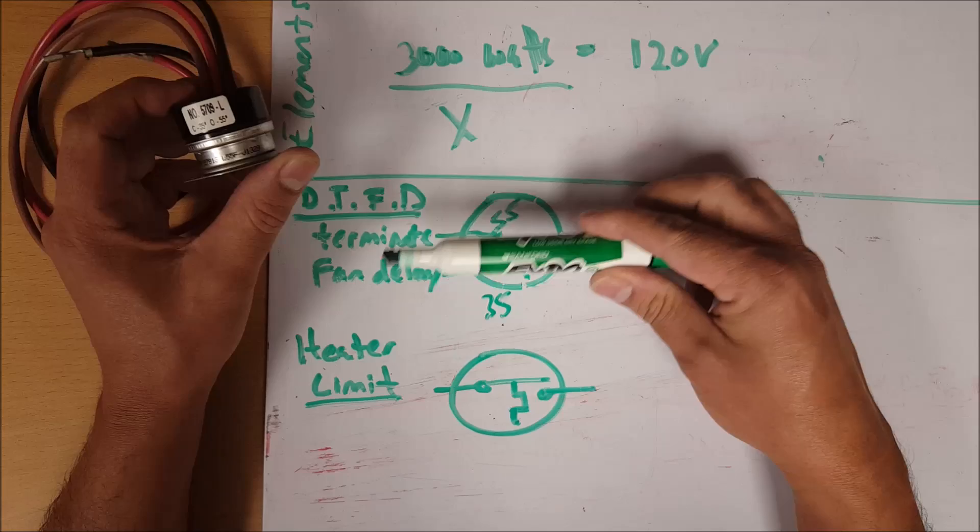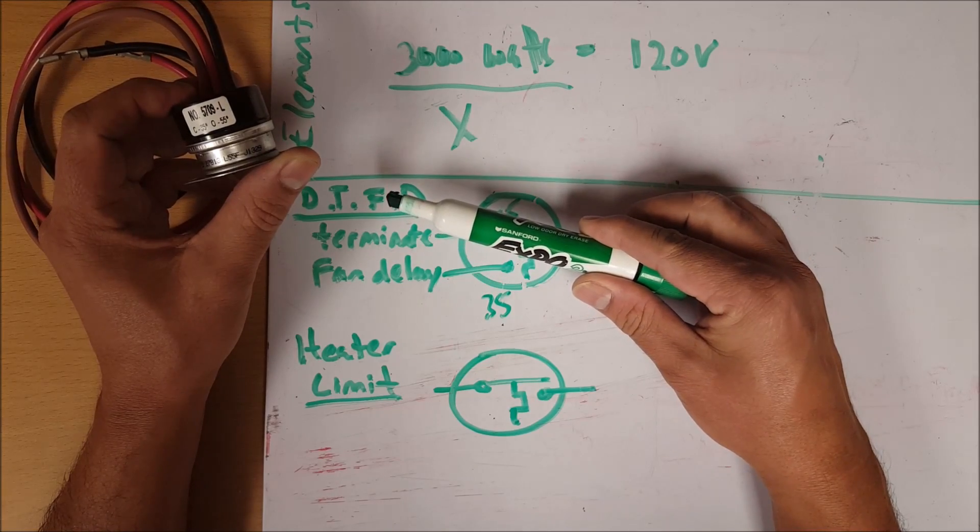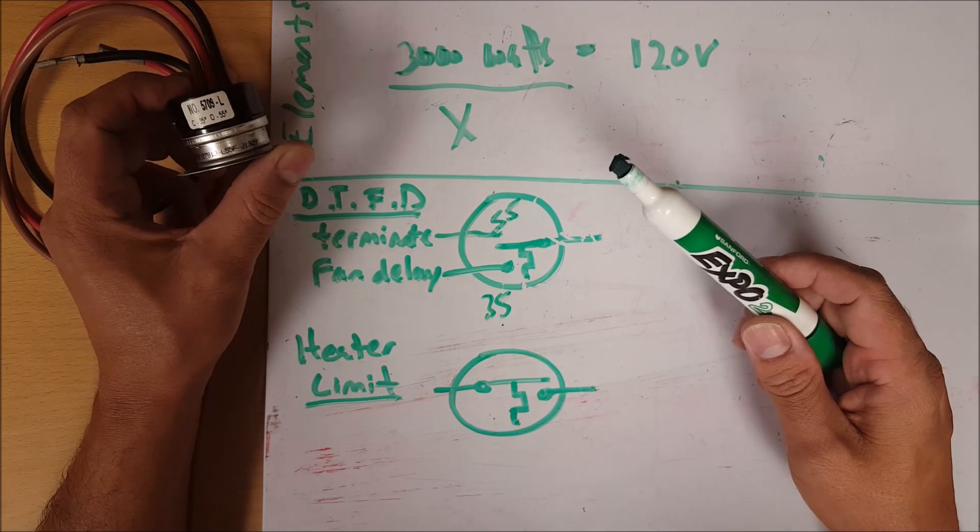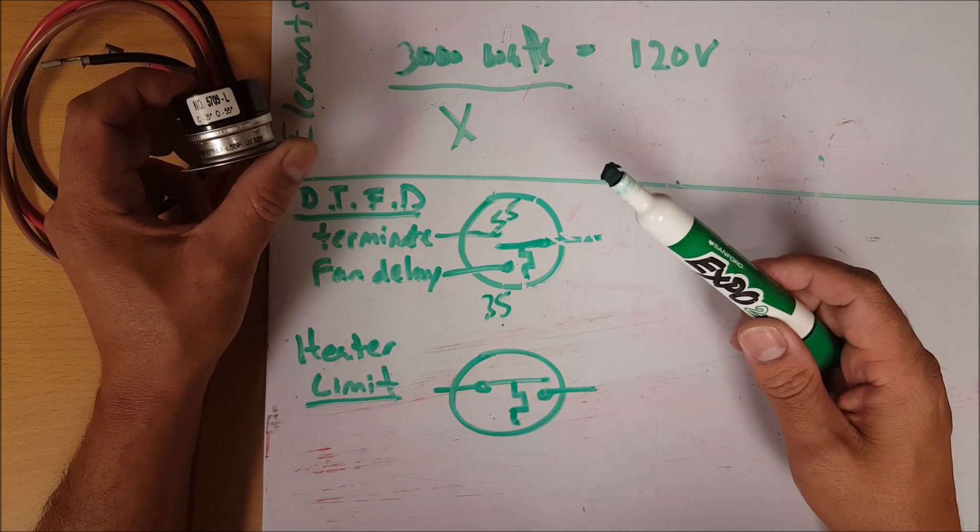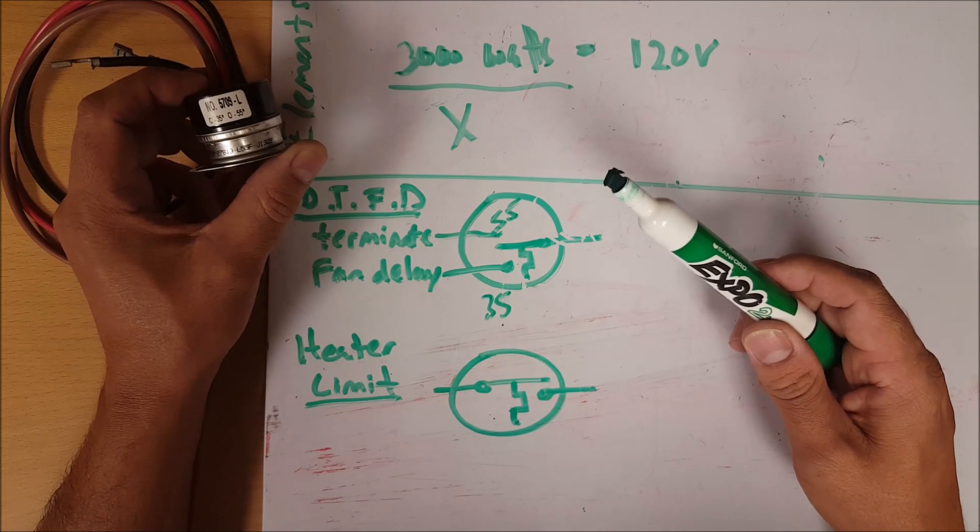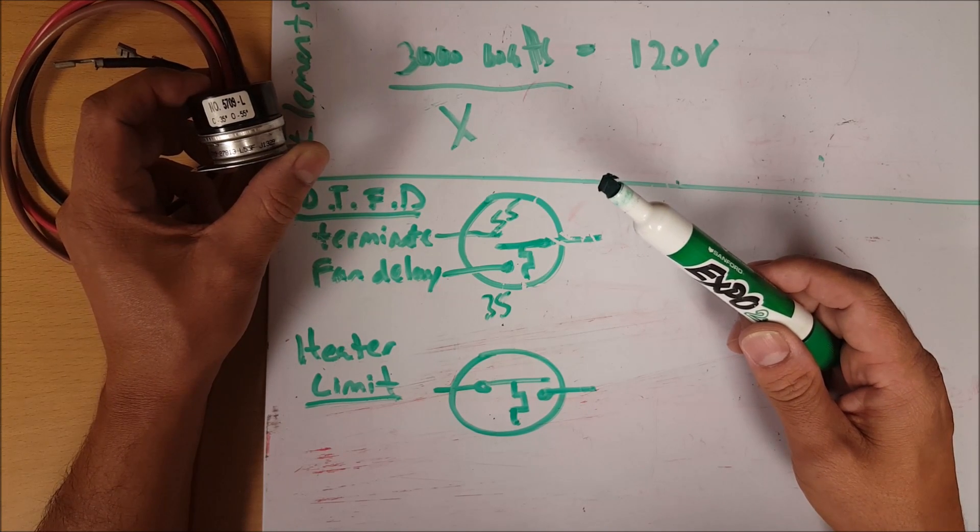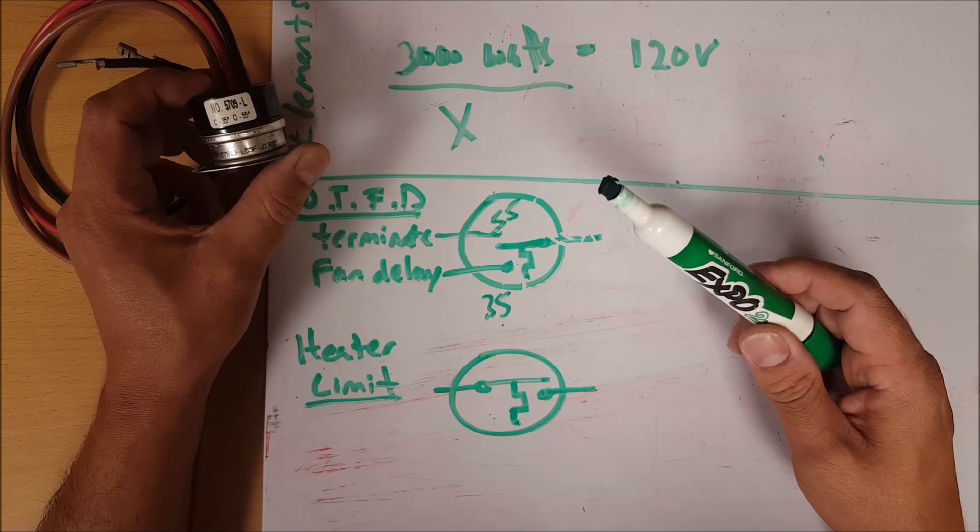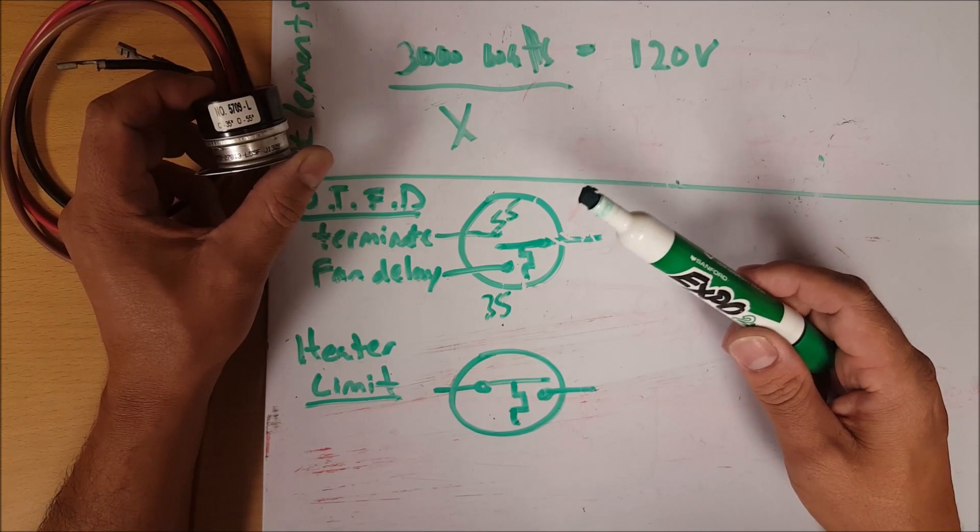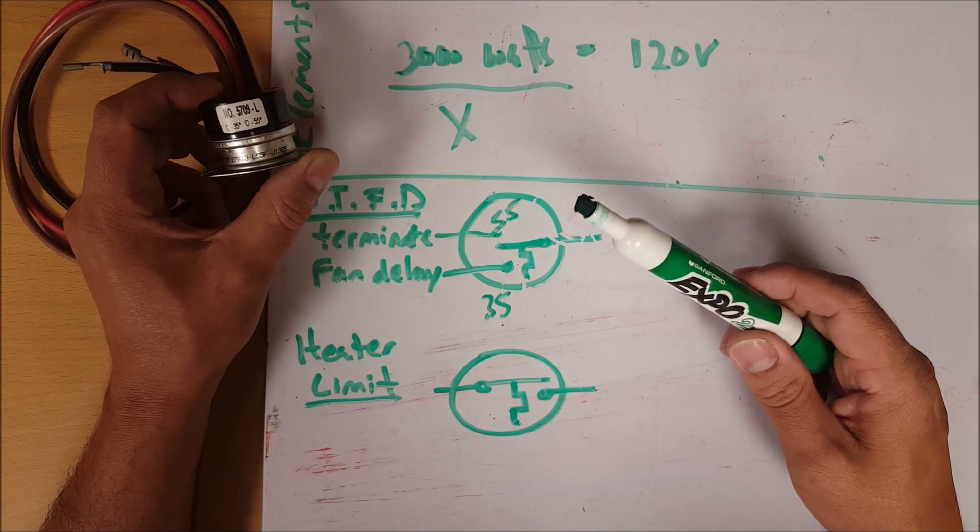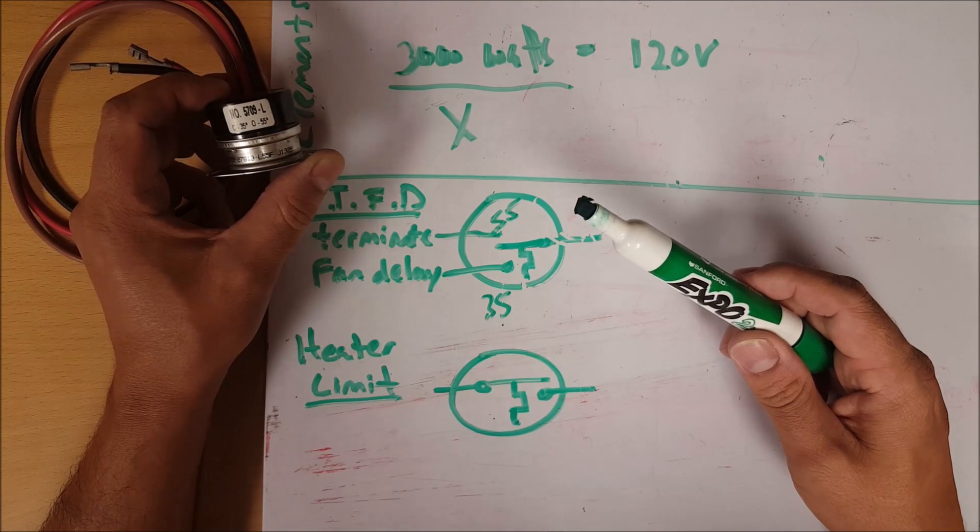During defrost when the temperature hits 55 degrees, it's going to close this switch. That's going to energize your solenoid on the back of your defrost timer and kick it out of defrost, put it back in refrigeration. Doesn't matter if there's any time left on the duration time of your defrost clock. If you're using this switch in conjunction with a termination switch on your timer, that's what's going to happen.